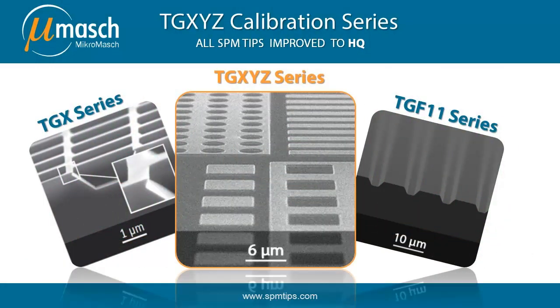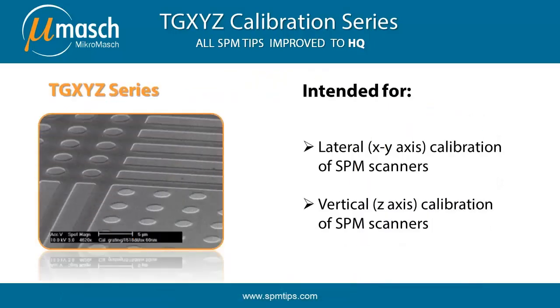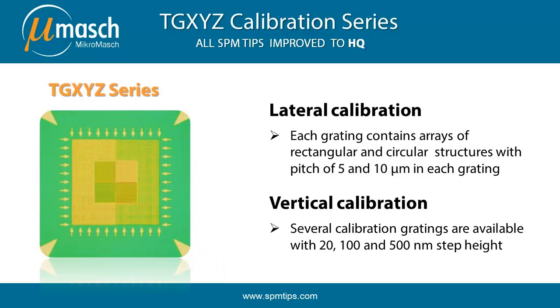We developed series of calibration standards with patterns with well-controlled pitch. One among them is the TGXYZ series of calibration gratings for X, Y and Z axis calibration. Part of the TGXYZ calibration grating is shown on the SEM image on the left. The TGXYZ calibration grating consists of two square areas as shown on the picture.